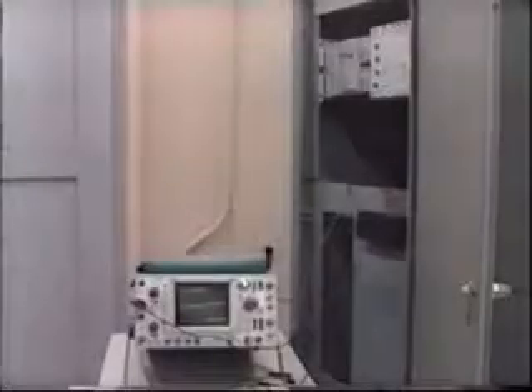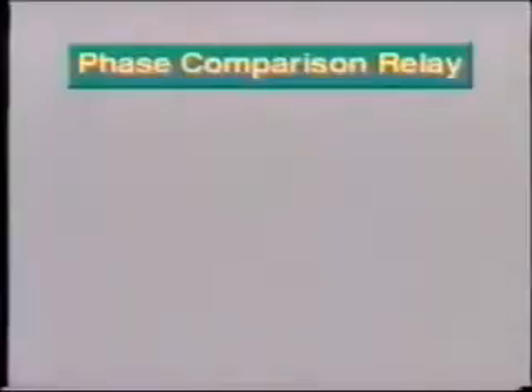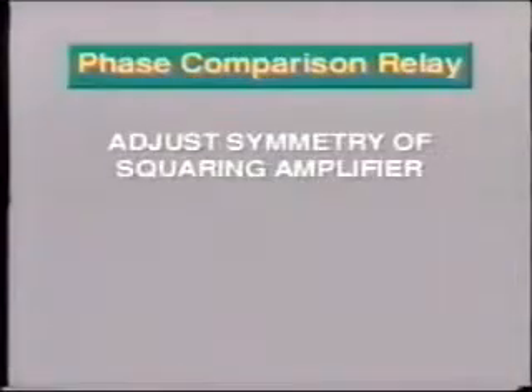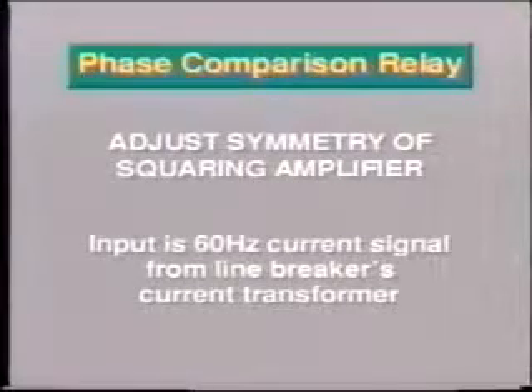Here is another practical example of the oscilloscope, testing a phase comparison relay. The manufacturer's instruction book tells you to adjust the symmetry of a squaring amplifier whose input is a 60 Hertz current signal from a line breaker's current transformers. You can obtain the waveform on the scope and adjust the appropriate potentiometer for equal on and off times of 8.33 milliseconds each. A regular multimeter could not give you the necessary picture for such a precise adjustment.